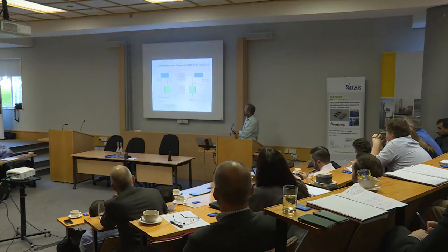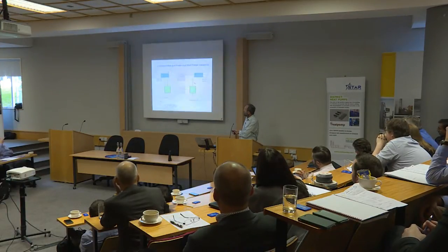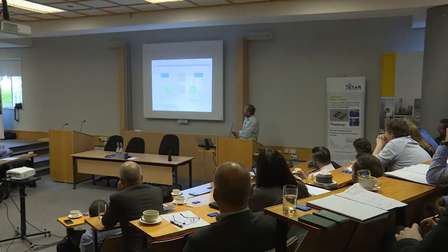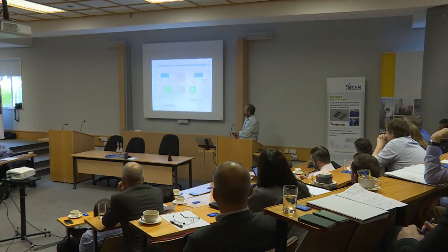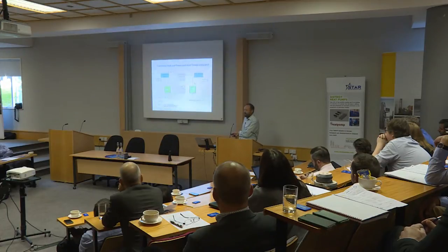You need some additional electricity to be made up, which requires additional fuel. So looking at this diagram, the CHP is producing heat because it sacrificed some electricity generation. You can treat the CHP very like a heat pump — it's meeting a heat demand and the extra electricity required is this figure here. CHP and the heat pump are virtually the same technology; they're two sides of the same coin.